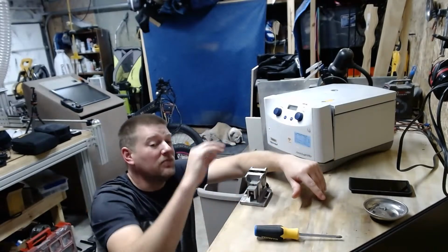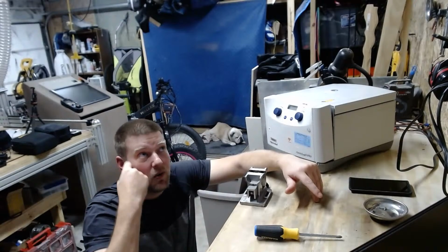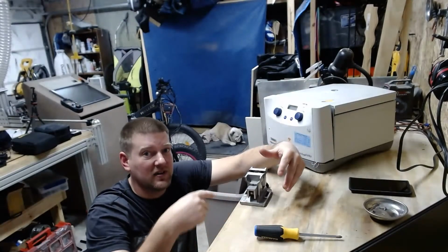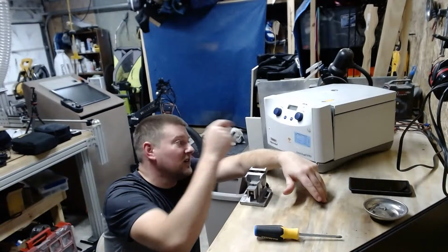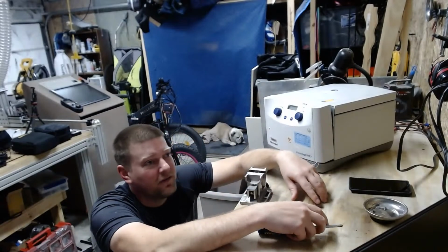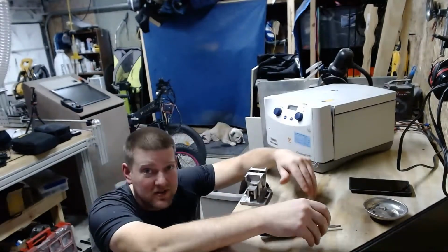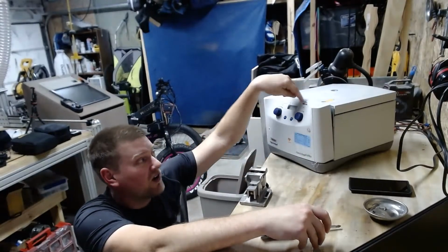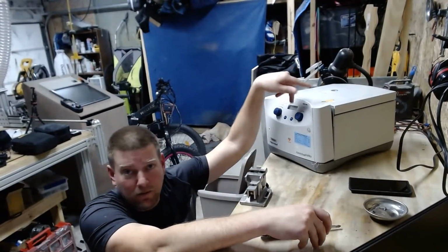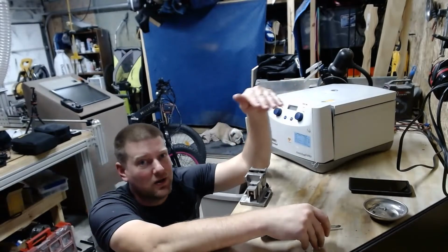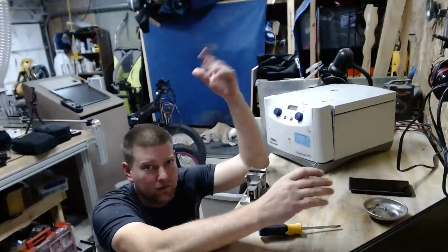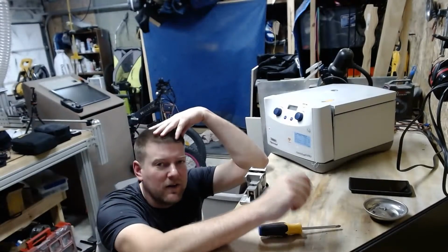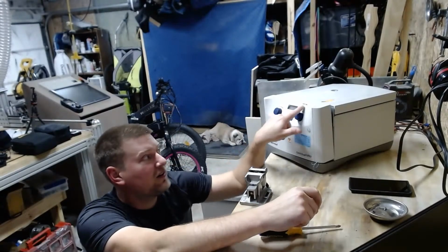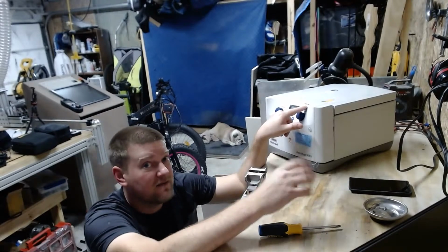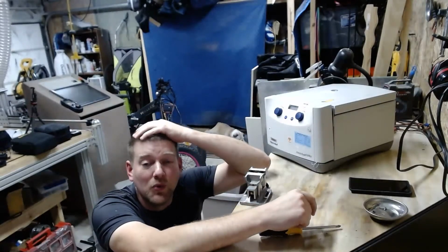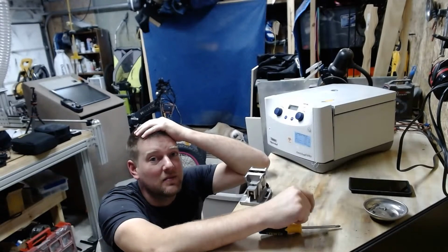So always, always return the unit to the exact same settings the user had when you walked up to it. Normally in surgical, only the old surgery devices would remember your last settings. But on laboratory equipment, it seems like every device I walk up to remembers the last setting. So I usually start at the maximum, which on this one is like 4,500 RPMs, and work down, like 35, 25, 1500. But if I leave it at 1500 RPMs and they're expecting 4,400 RPMs at 5 minutes, their sample could be ruined, because of something I did.